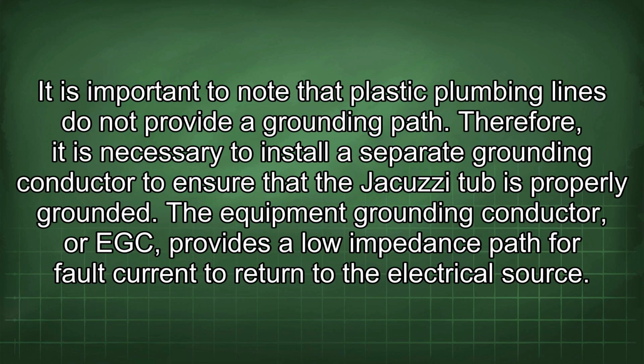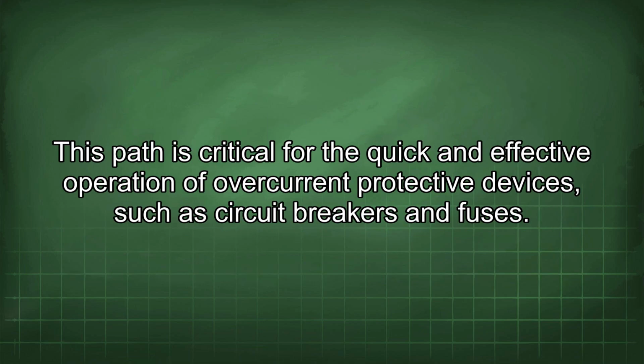It is important to note that plastic plumbing lines do not provide a grounding path. Therefore, it is necessary to install a separate grounding conductor to ensure that the jacuzzi tub is properly grounded. The equipment grounding conductor, or EGC, provides a low impedance path for fault current to return to the electrical source. This path is critical for the quick and effective operation of overcurrent protective devices, such as circuit breakers and fuses.